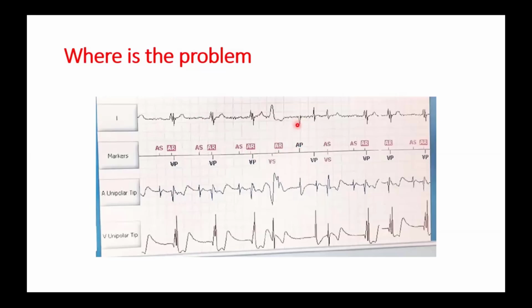The lower rate is not set here. So this atrial pacing is not followed by an atrial electrogram. So this is malcapture, or the threshold needs to be increased, from this paced beat in the atrium, which is not followed by an atrial electrogram. Look at the atrial channel.